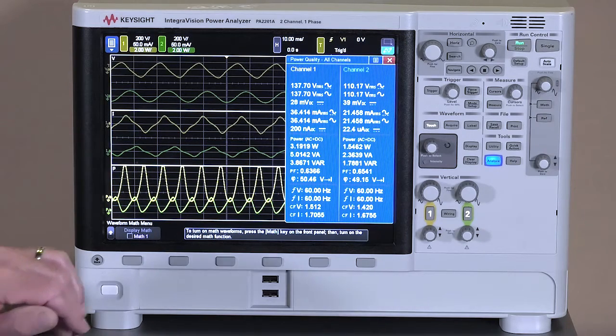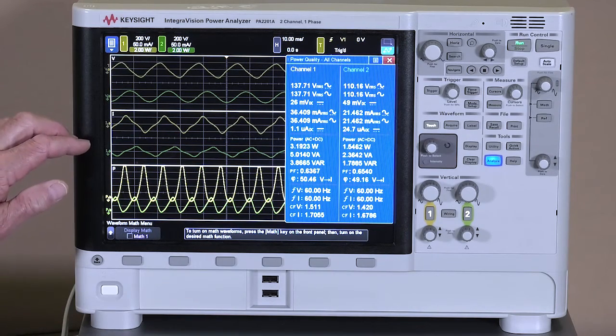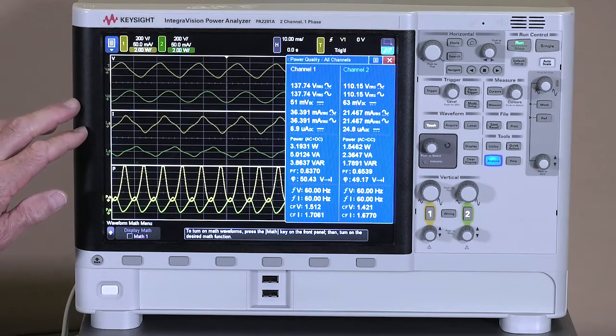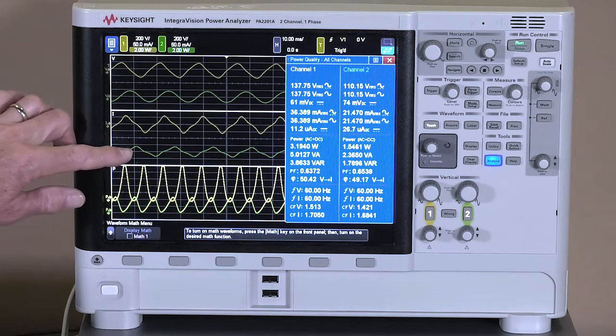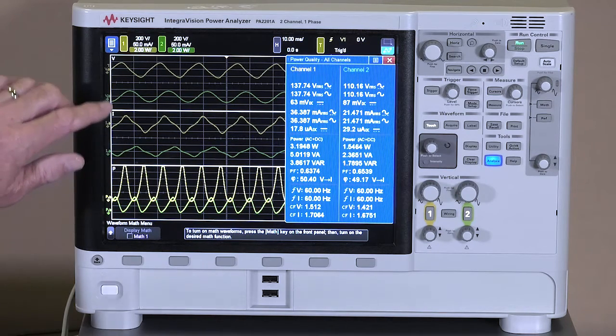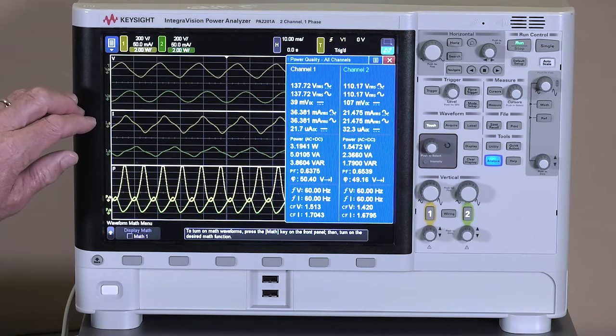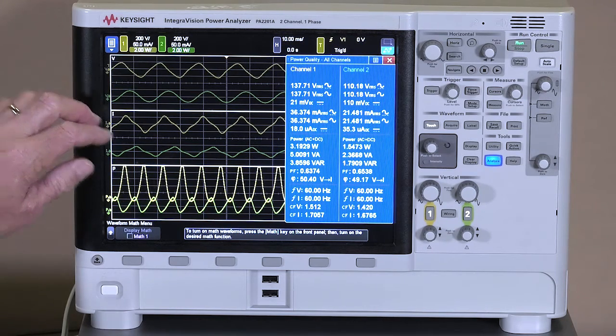One other interesting thing is when we first looked at the power measurements on our AC source, we noticed the motor has a pretty good power factor at 95%. What that means is when you add these two currents together, it should be right on top of our voltage measurement with no difference in phase.